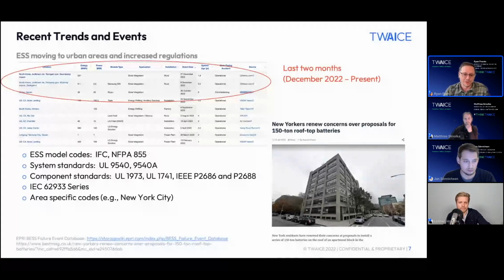There are also system standards that differ from the codes and that the codes reference, like UL standards 9540 and 9540A for fire testing in the US. But also internationally, there is a growing body of safety standards, including those under IEC 62933, the body of work under Technical Committee 120 at the IEC, which will be referenced and promulgated in countries that typically reference IEC standards.